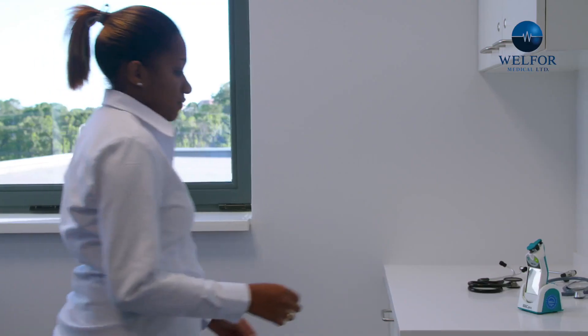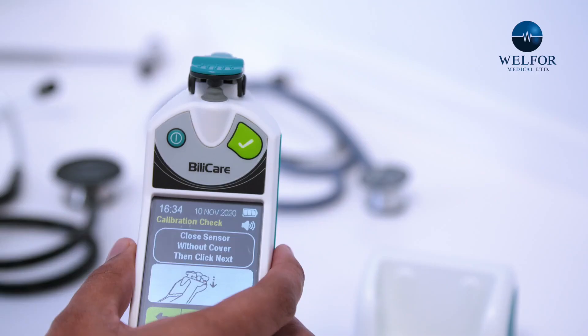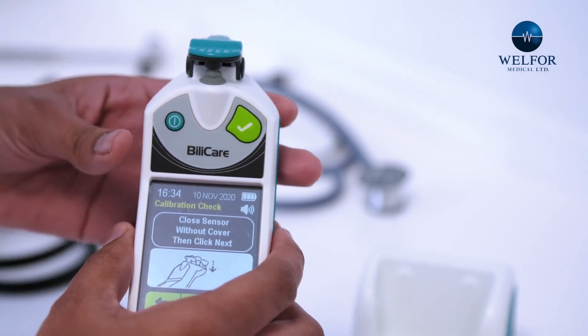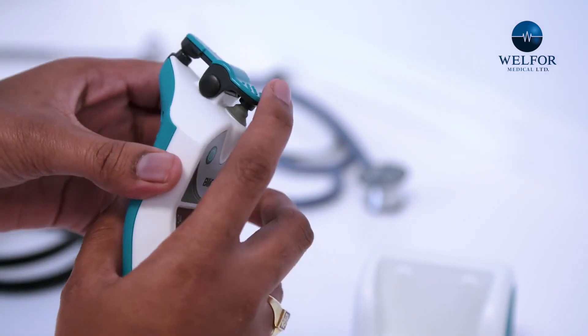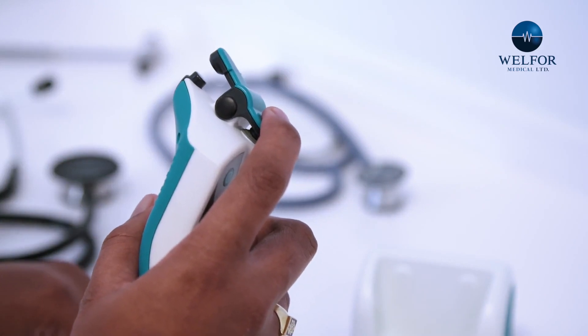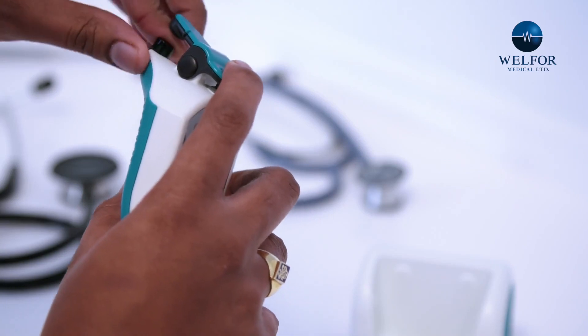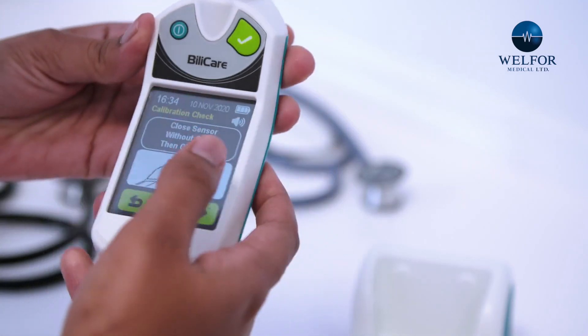The BiliCare is a great innovation in neonatal care. This cutting-edge diagnostic tool is used to determine jaundice in neonates through a non-invasive bilirubin measurement. By placing the light sensor on the baby's ear, the amount of light absorbed by the bilirubin is calculated according to a customized algorithm and feedback is obtained in seconds. We can do this without the need for blood tests, drastically improving the jaundice screening process.